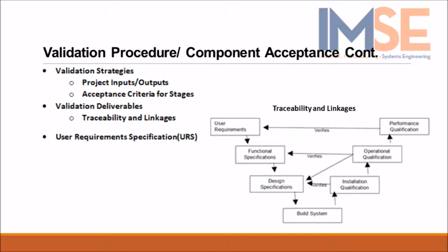Traceability and linkages. This document links the URS, FRS, design specifications, and the testing specifications per the V model to the right. User requirement specifications. This document describes what the equipment is intended to do and all essential requirements such as production rates, operating ranges, etc. It is usually developed by the owner. This document links to the PQ document, which tests for each of the requirements.